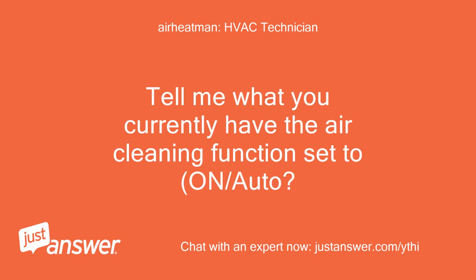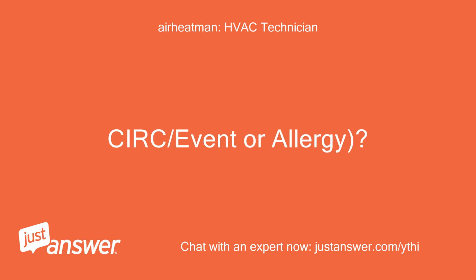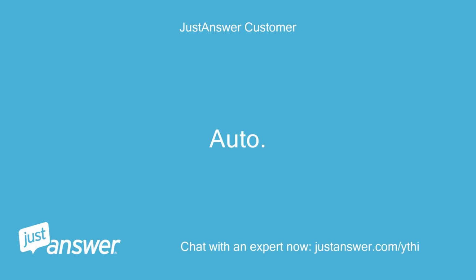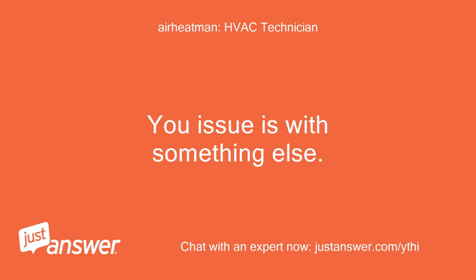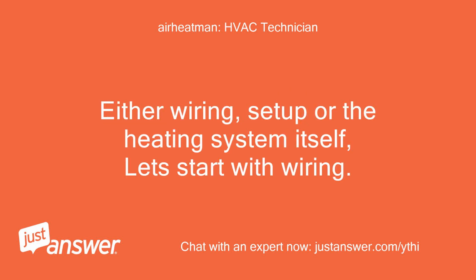Tell me what you currently have the air cleaning function set to, on/auto? Circ/event or allergy? Auto. Okay, in auto mode, air cleaner should not be on unless heat or cool is being called for. Your issue is with something else. Either wiring, setup or the heating system itself.